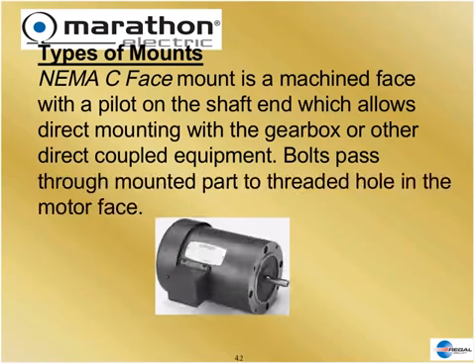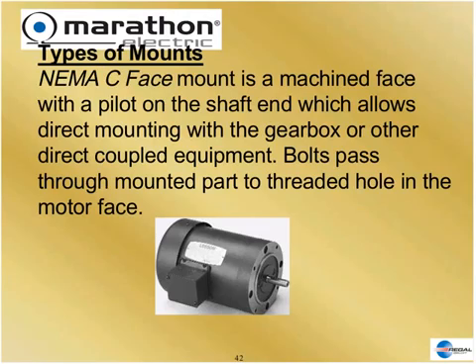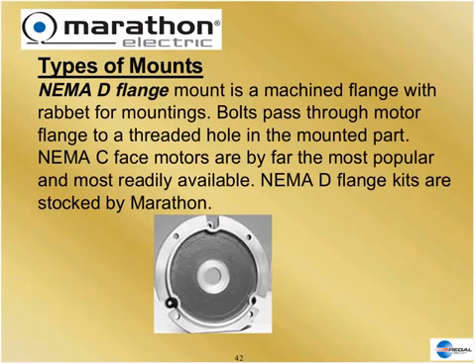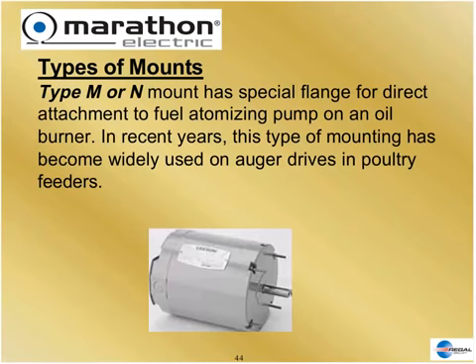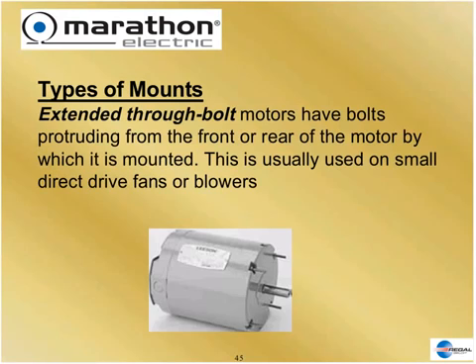Sometimes we want to mount the motor up against a bulkhead or into a gearbox, so we use a flange mount. The C-face has tapped holes so you can bolt the motor directly to a wall, bulkhead, or gearbox without needing the foot. The D-flange and N or M-flange are similar options. This type of flange is used on oil burner furnaces and, in recent years, auger drives in the poultry industry. Sometimes we just extend the bolts that hold the motor together and let the customer use those bolts to mount to his bulkhead or wall.